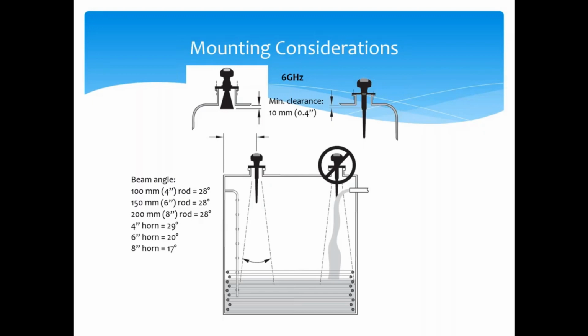We got a couple more questions. Are there multiple types of coatings on the radar horns depending on the material being measured? Yeah, absolutely, depending on the dust or powder you're measuring, you could have different types of coatings. Is that what's being asked, or is this more about materials of construction? Yes, standard horns are 316 stainless. We also make horns out of Hastelloy, and horns made out of other materials. In our case, we do a Teflon encapsulated horn, and a horn made entirely out of Kynar. So yes, we have different options depending on the media or what's off-gassing inside your vessel.